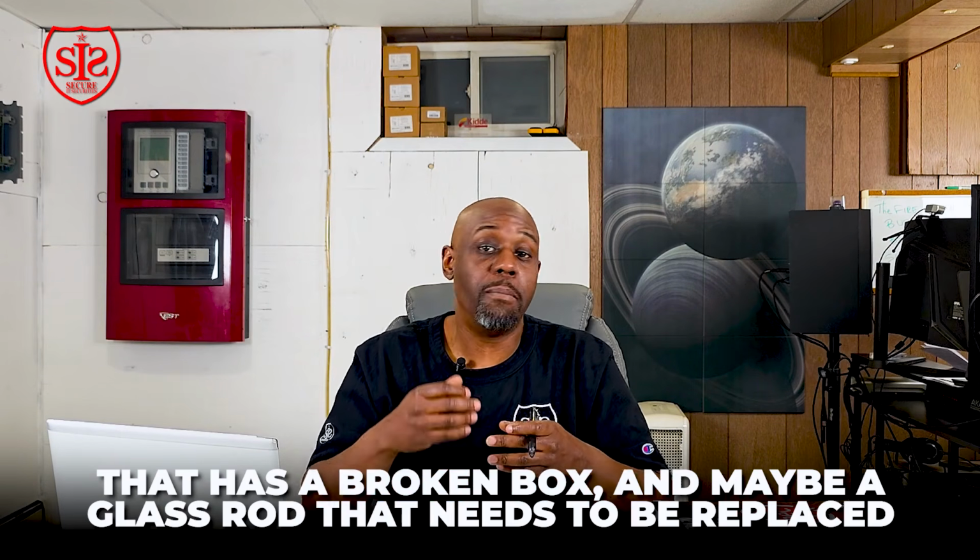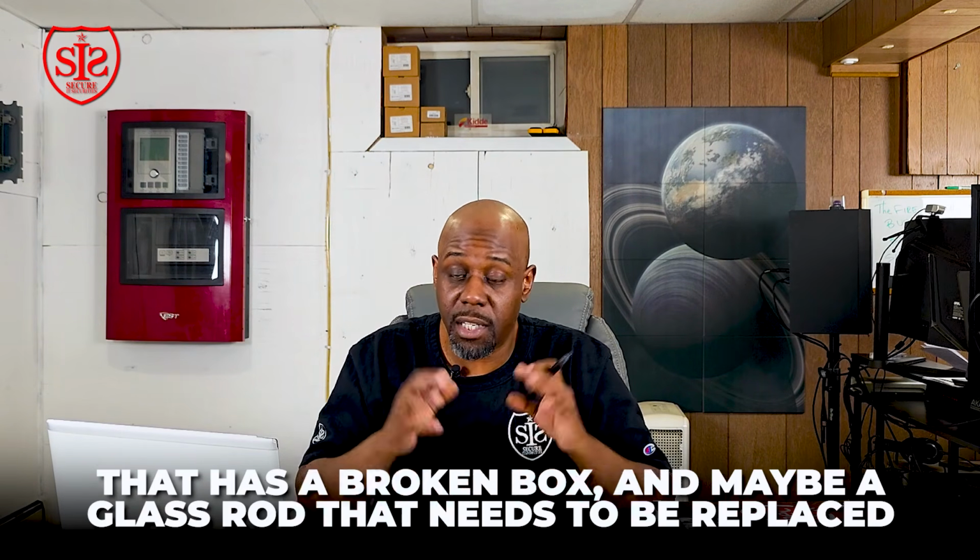Now let's talk about some reasons why your fire alarm system may fail inspection. You may have a pull station that has a broken box. It may be a glass rod that needs to be replaced. Something as simple as a glass rod, yes, you can actually write that down. It doesn't fail the system, but it's a problem that we have to come back and put a glass rod in this fire alarm pull station.